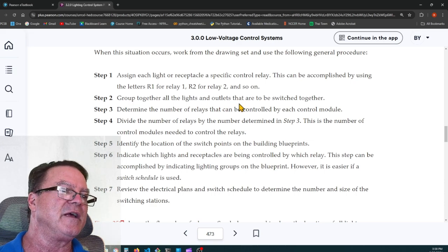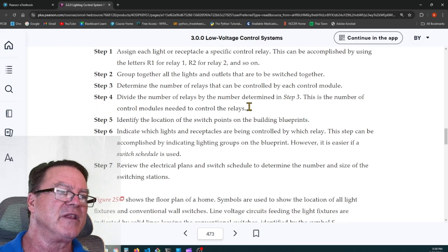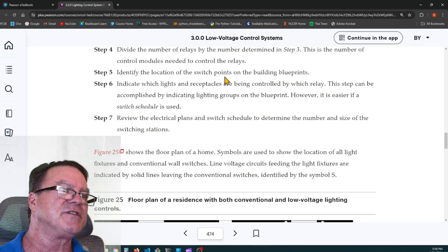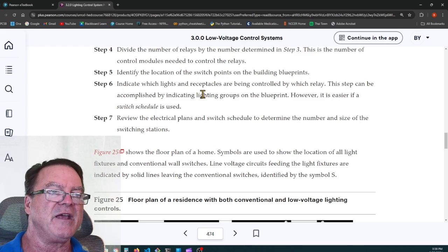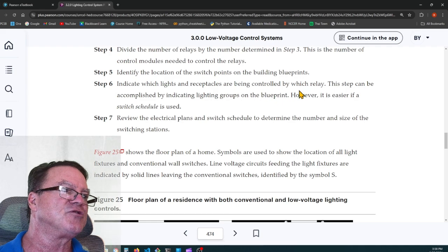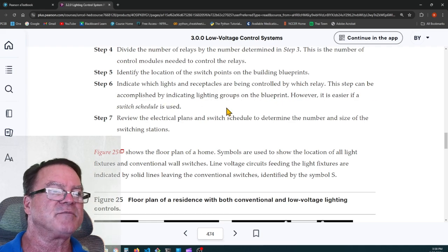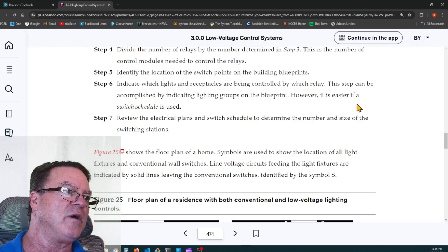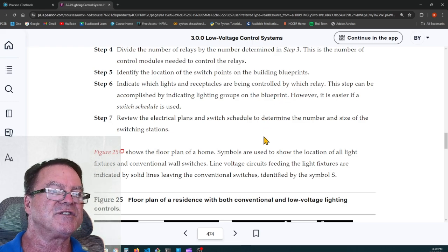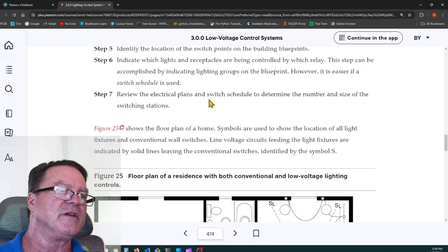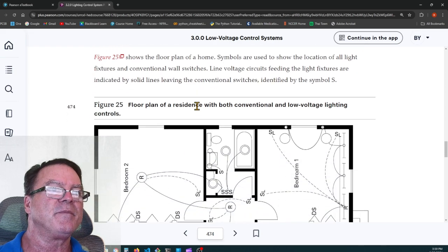Group together all the lights and outlets that are to be switched together. Determine the number of relays that can be controlled by each control module. Divide the number of relays by the number determined in step 3. This is the number of control modules needed to control the relays. Identify the location of the switch points on the building blueprints. Indicate which lights and receptacles are being controlled by which relays. This step can be accomplished by indicating lighting groups on the blueprints. However, it's easier if a switch schedule is used. And review the electrical plans and switch schedule to determine the number and size of switching stations.